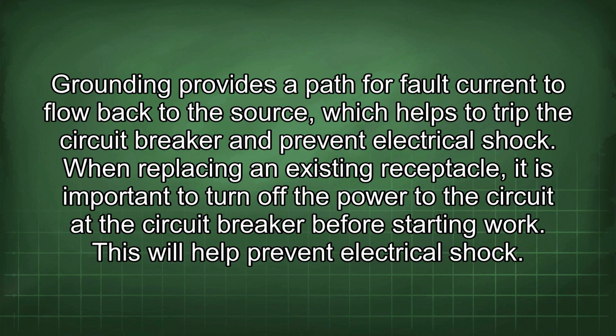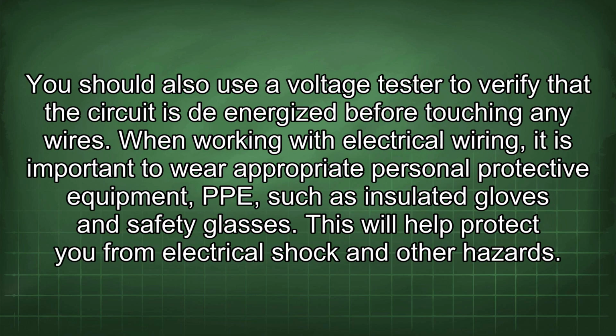When replacing an existing receptacle, it is important to turn off the power to the circuit at the circuit breaker before starting work. This will help prevent electrical shock. You should also use a voltage tester to verify that the circuit is de-energized before touching any wires. When working with electrical wiring, it is important to wear appropriate personal protective equipment, PPE, such as insulated gloves and safety glasses. This will help protect you from electrical shock and other hazards.